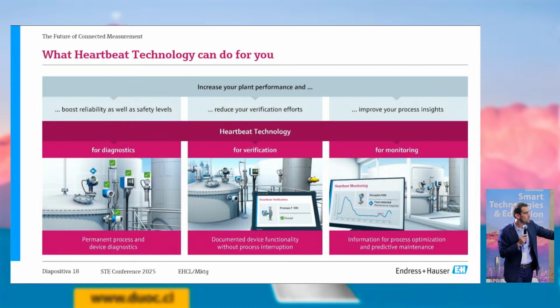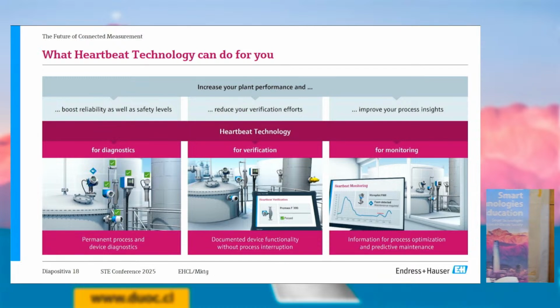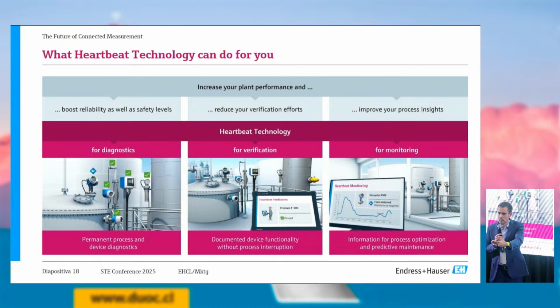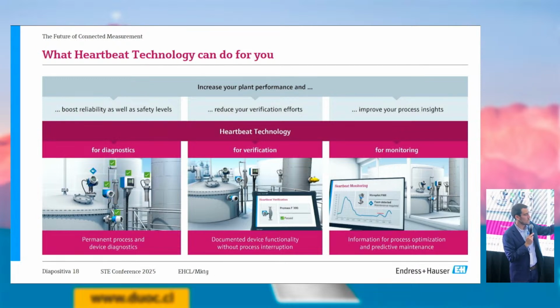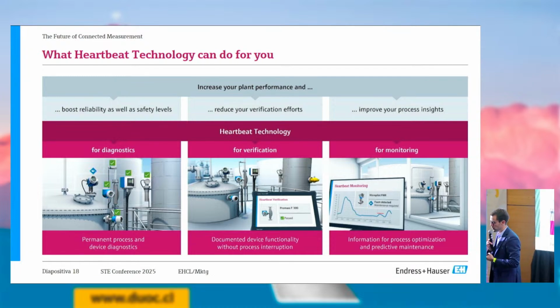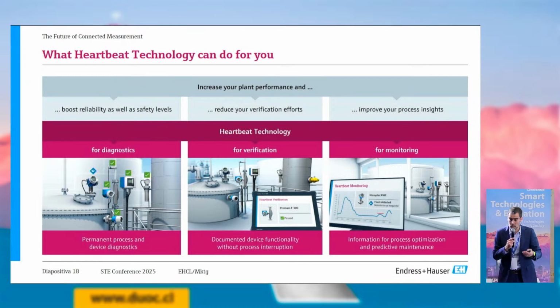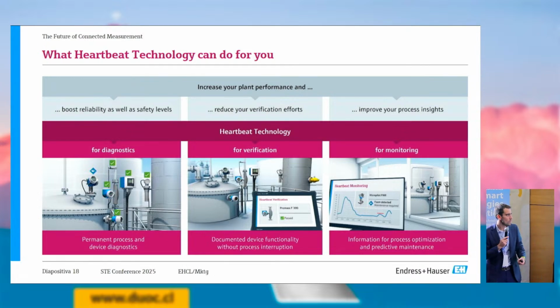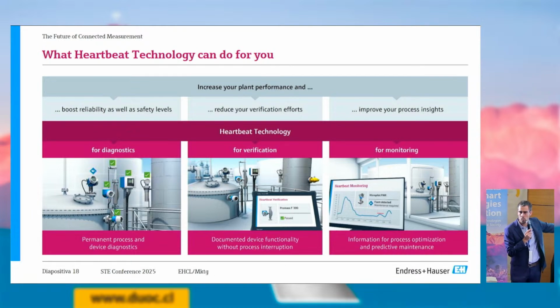That is reactive. Verification means documenting device functionality to get a PDF file that fulfills, for example, ISO 9001 certification. I'll talk about this in more detail in a couple of minutes, but you can get a verification report. That's proactive maintenance: get the report, go to the field, confirm the device is fine, move to the next one, and avoid getting a red alert later.